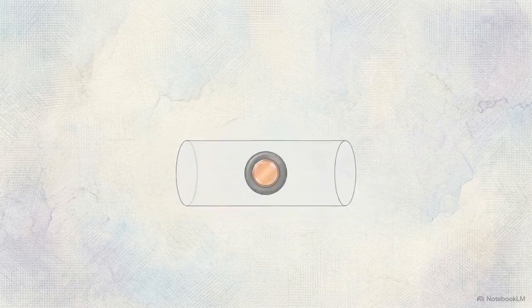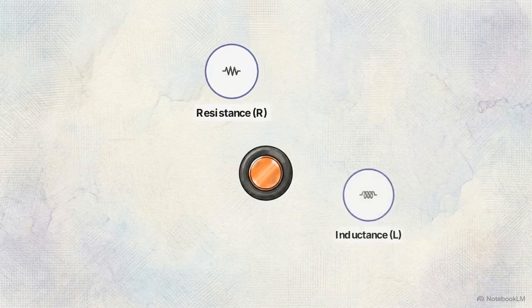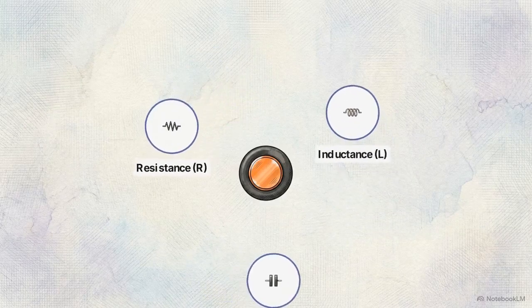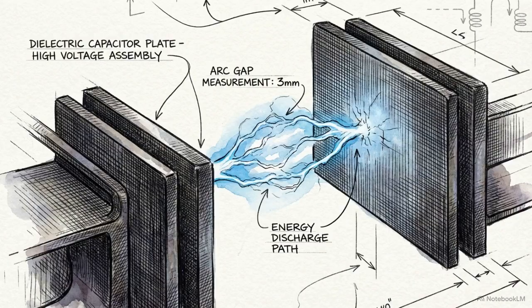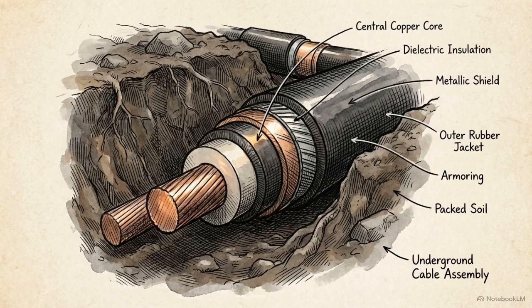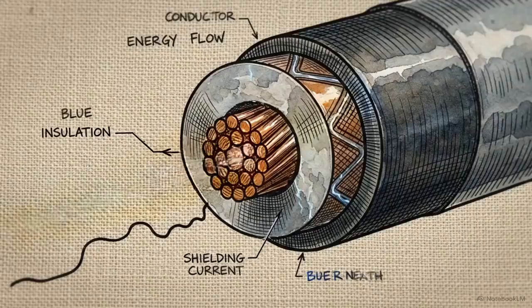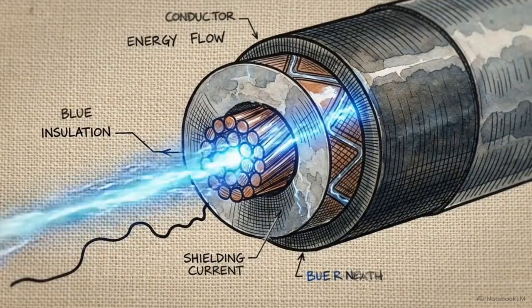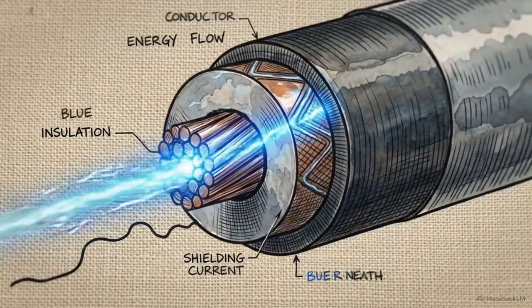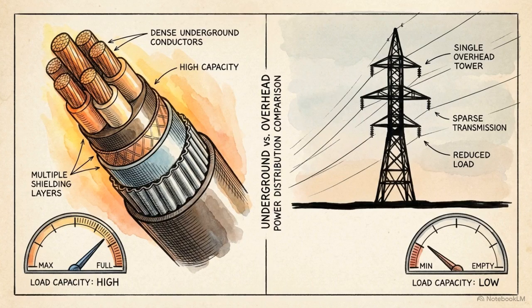A transmission line is not a passive, empty pipe. Every wire possesses three built-in electrical properties: resistance, inductance, and capacitance. Capacitance is the ability to store an electrical charge. We see this heavily in underground power cables. Because their internal wires are tightly packed together inside heavy insulation, they naturally generate their own reactive power as current flows through them. Overhead transmission lines have a much lower capacitance per mile than buried cables.